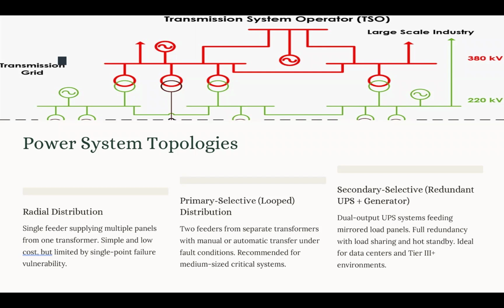The advantages of this topology are that we have full redundancy, which ensures continuous uptime. It supports load sharing and hot maintenance. On the other hand, there is a high installation and maintenance cost for this topology, and it requires a careful design so we can avoid circulating current between the sources. So we need to consider these trade-offs when we choose the power system topology between these three choices that IEEE 1100 gave us.